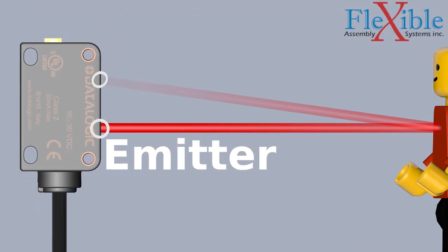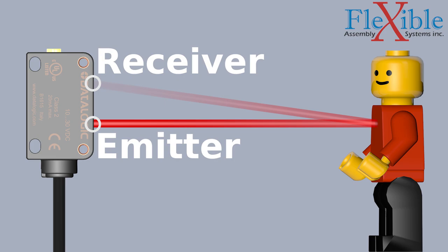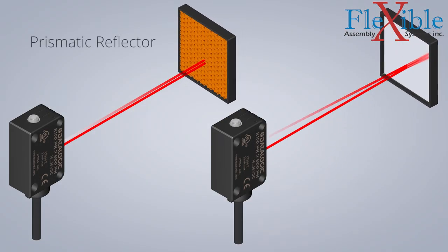Just like retro-reflective sensors, the emitter and receiver for diffuse sensors are located in one housing. The main difference is that diffuse sensors use the target to send light back instead of a dedicated prismatic reflector.